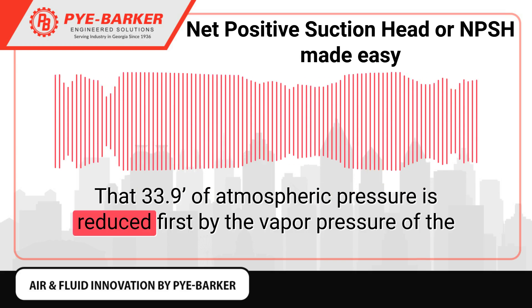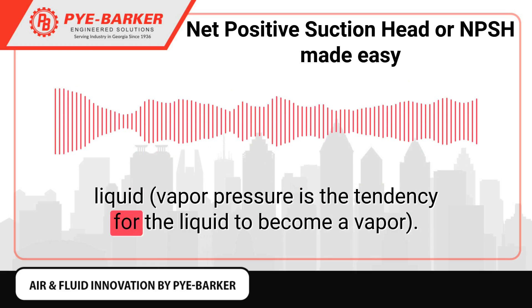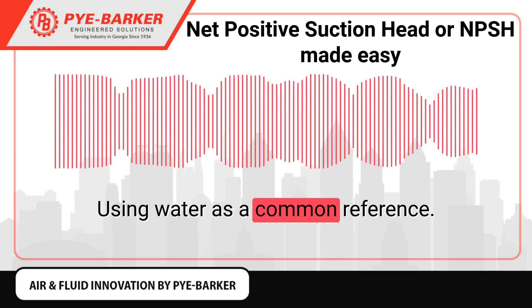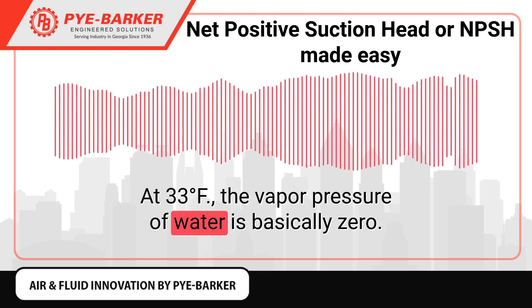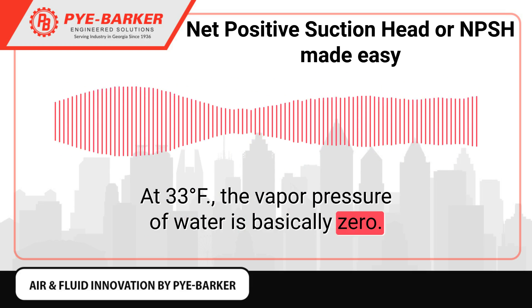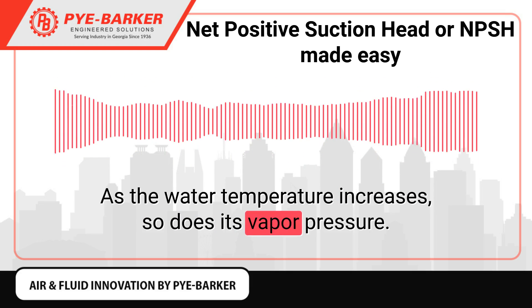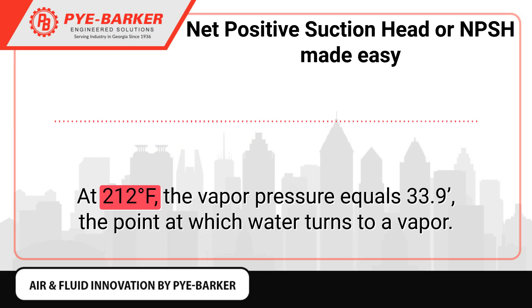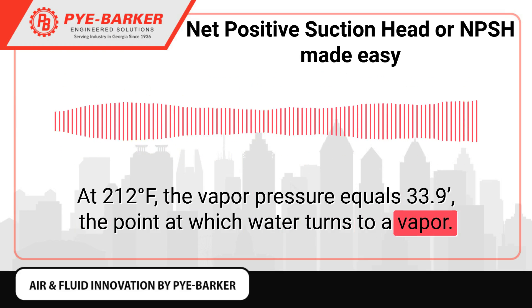That 33.9 feet of atmospheric pressure is reduced first by the vapor pressure of the liquid. Using water as a common reference, at 33°F the vapor pressure of water is basically zero. As the water temperature increases, so does its vapor pressure. At 212°F, the vapor pressure equals 33.9 — the point at which water turns to a vapor.